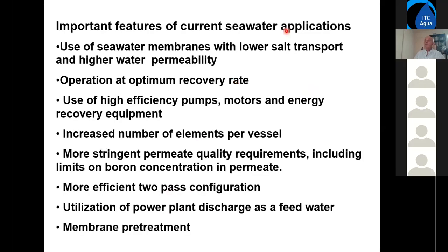So in the current seawater application, using membrane with lower salt transport and higher water permeability, you may remember we discussed this in module one, we try to operate at optimum recovery rate, which is, as I said, between 40 to 55%, using pumps and motors, energy equipment with very high efficiency to reduce energy consumption. Increased number of elements per vessel from 6 to 7, now it's already 8. This is on the positive side. The negative side, more stringent permeate quality requirements, including limits on boron concentration in permeate.